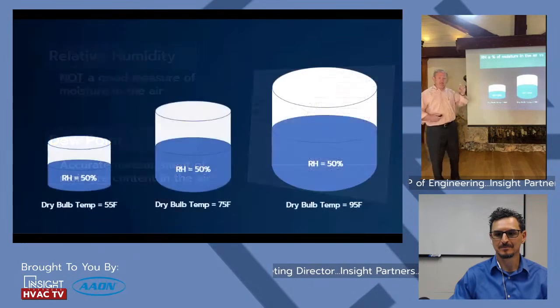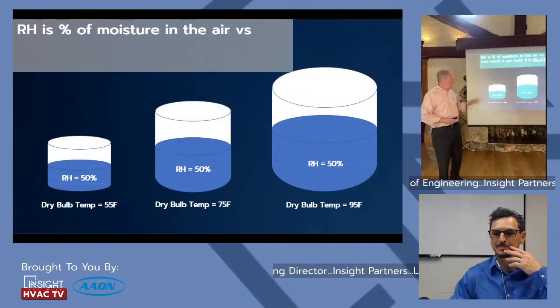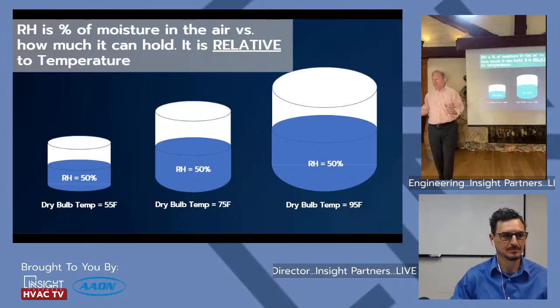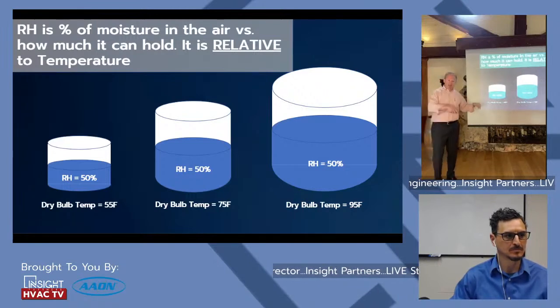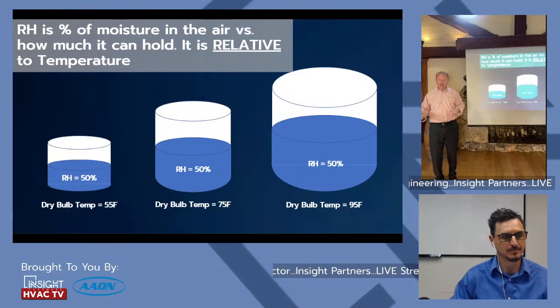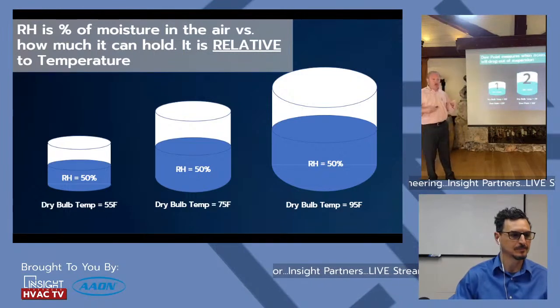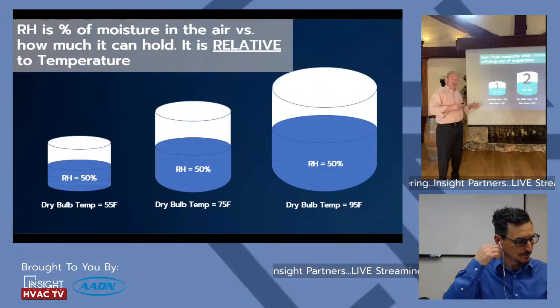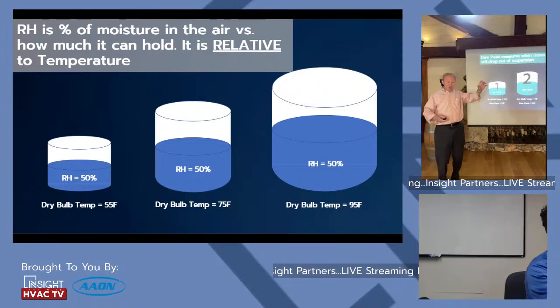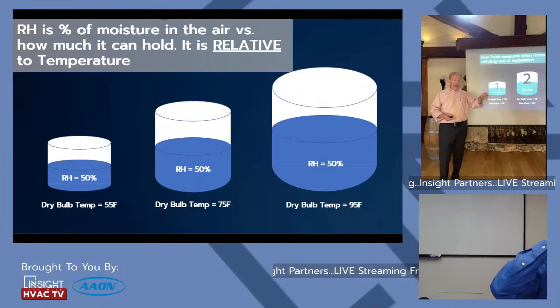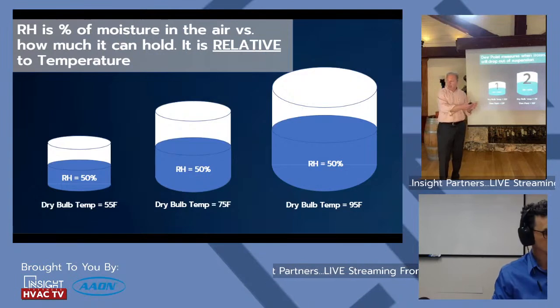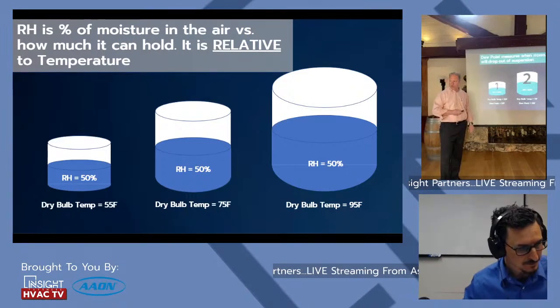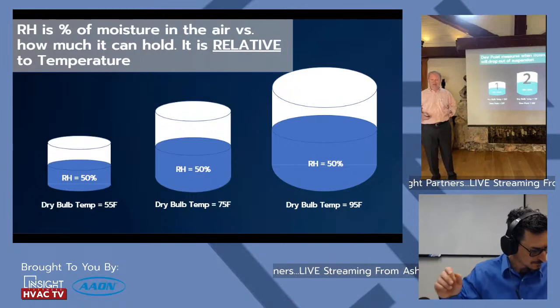Relative humidity is the percent of moisture in the air versus how much it can hold. So at dry bulb temperatures of 55, 75, or 95 degrees, you can still have 50% relative humidity but with very different actual moisture content — especially here in Orlando. Dew point measures the temperature at which moisture will drop out of suspension. We've got to get that moisture to drop out of suspension — like condensation on a cold glass of ice water. That's the temperature at which it drops, but the quantity of moisture is completely different.